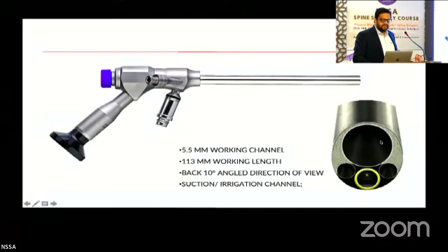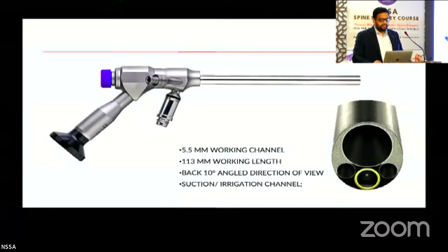It varies. The most common endoscopes in India right now have a 1 centimeter outer diameter and a 6 millimeter working channel. The benefit is that you can put bigger instruments inside. They're more sturdy. They don't break easily. But then you need a 1 centimeter outer diameter, so it is significantly bigger to put inside the spinal canal while doing decompression. When you are retracting the nerve root and trying to do discectomy, the 1 centimeter outer diameter sheath can also cause some neuropraxic injury on the nerve root due to traction. A smaller scope in that case would be better, but a smaller scope again means smaller and flimsy instruments. So you have to have your own cutoff, what is going to be suitable for your case and your practice. And of course, your teacher, your mentor, will be the best person to guide you on the pros and cons of whichever system you're going to buy.